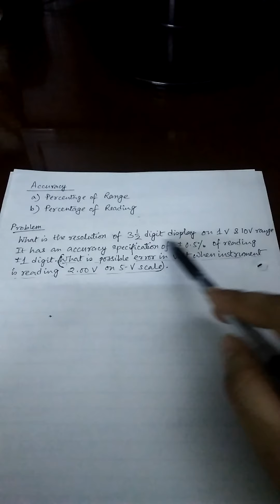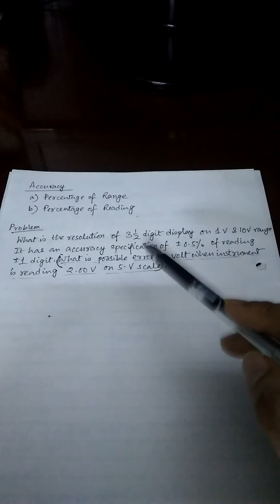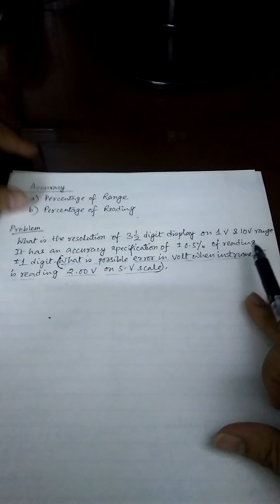And when we consider the 3.5 digit display, the 4th digit comes in, indicating either 0 or 1, hence we call this a half digit. That is actually increasing the range. A 3.5 digit display can measure up to 1999 millivolt. That means the range increases from 999 to 1999 millivolt when converting the 3 digit display to a 3.5 digit display.